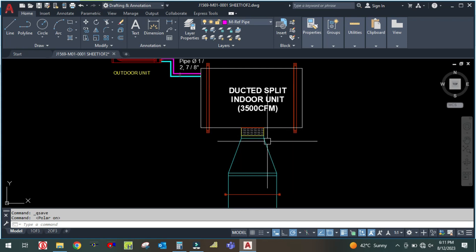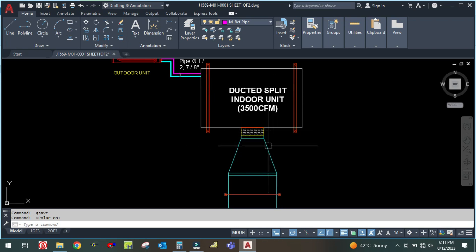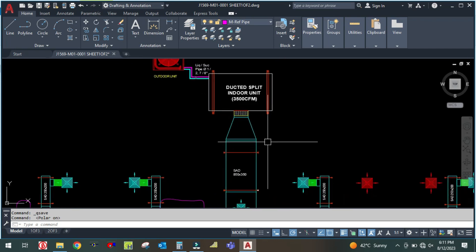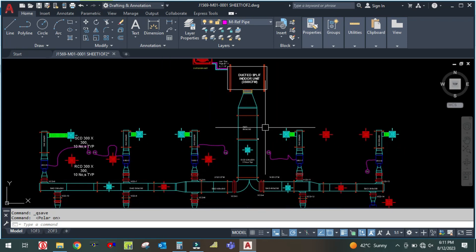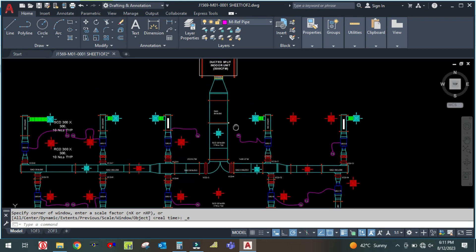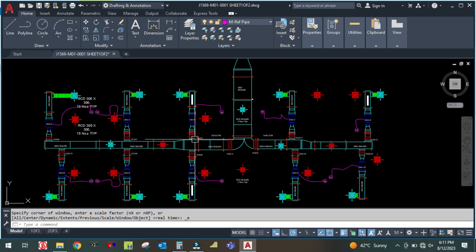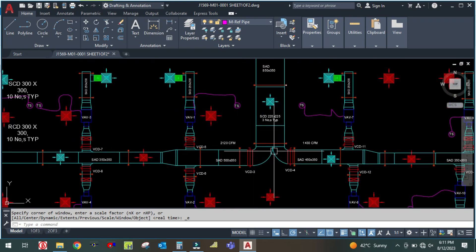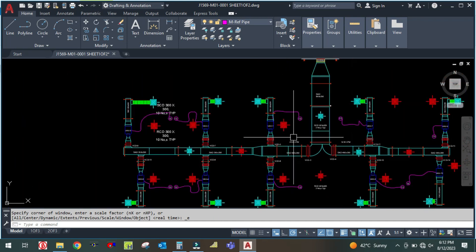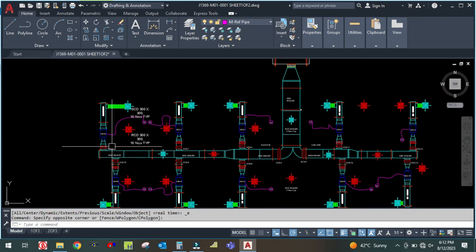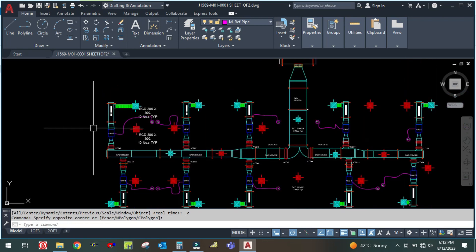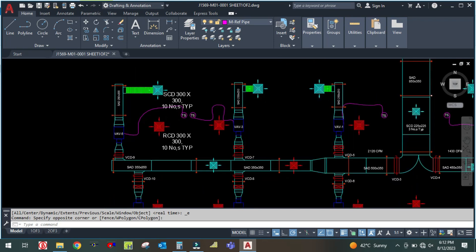Each branch is serving individual rooms — this design is for 10 rooms. In each branch there are VAVs, and the VAVs are connected with thermostats, so the temperature can be controlled individually in each room. The thermostat controls the VAV. Each VAV contains an actuator, and this actuator is controlled by the thermostat. Whenever there is a demand in the room, the thermostat sends a signal to the actuator and it will open or close. TS stands for thermostat and VAV stands for variable air volume.